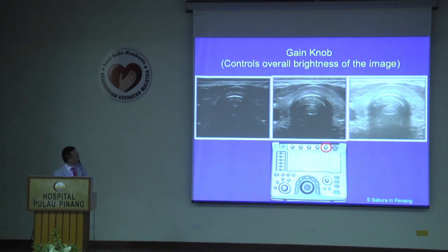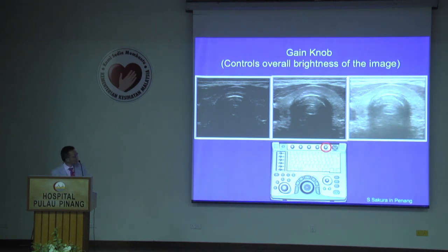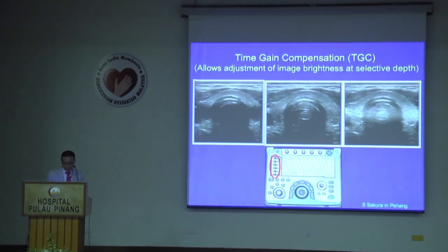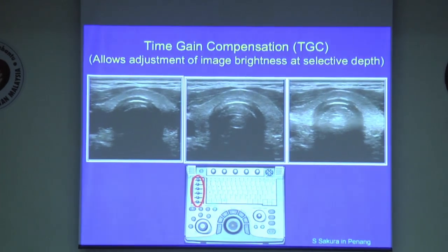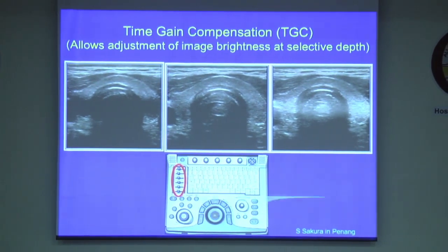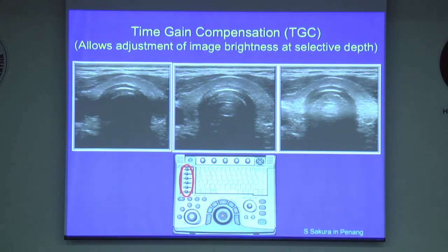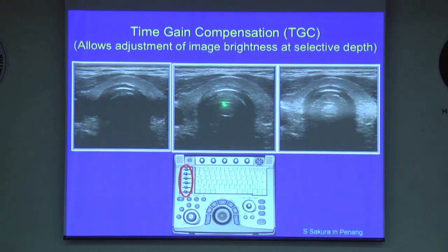Probably the gain knob is most likely the knob you use most frequently. This adjusts the overall brightness of the ultrasound image, and inadequate or excessive gain can cause blurring of tissue boundaries as well as loss of information. Most machines have five to ten slide controls grouped together — these are TGC, or time gain compensation controls. They adjust gain in specific areas of the image. The middle image showed an optimal TGC setting while the others are incorrect settings.